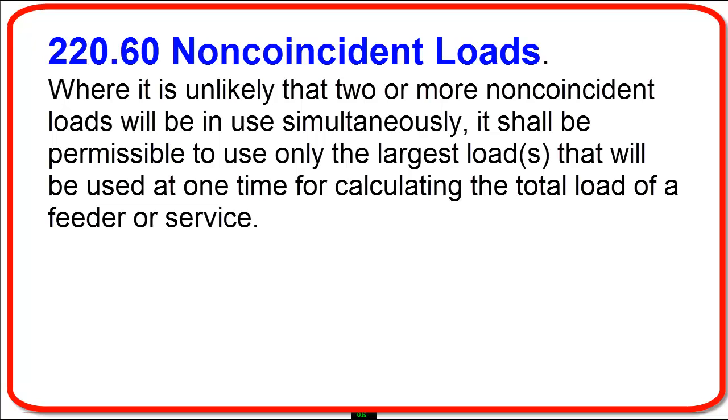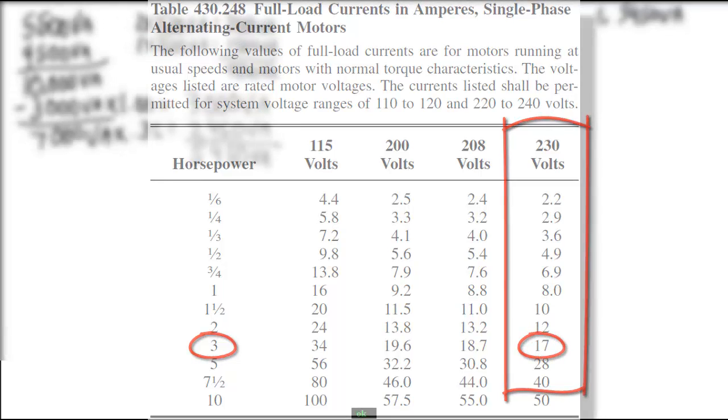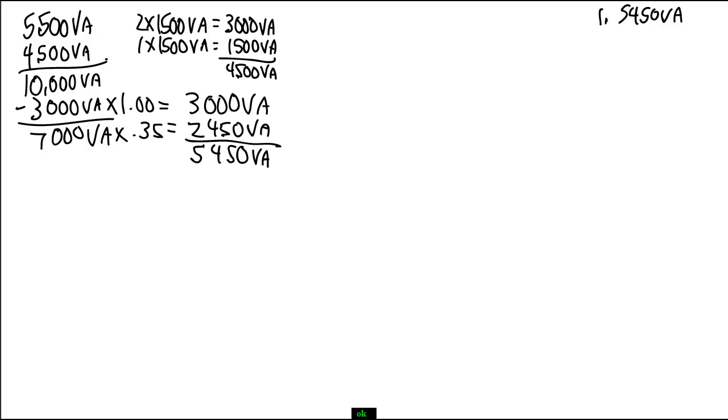Because we are looking at a motor load, we do have to look into another article to figure out what our ampacity is going to be for that. We need to look at Table 430.248. That is full load current in amps for single-phase alternating current motors. If we go down to 3 horsepower and we go over to 230 volts, that gives us 17 amps. So I need to take my 17 amps, and I need to take that times 240 volts, and that's going to give us 4,080 VA.